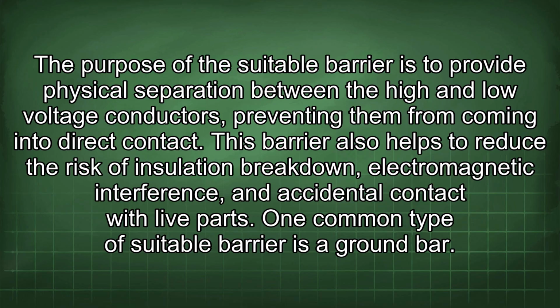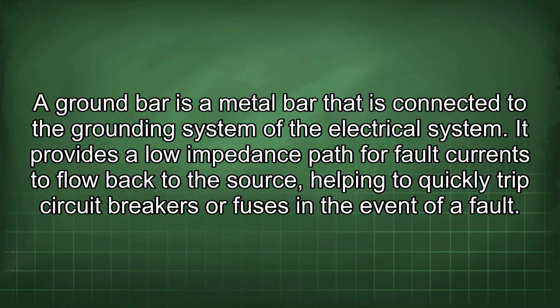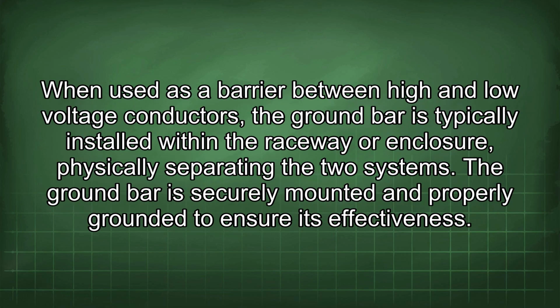One common type of suitable barrier is a ground bar. A ground bar is a metal bar that is connected to the grounding system of the electrical system. It provides a low impedance path for fault currents to flow back to the source, helping to quickly trip circuit breakers or fuses in the event of a fault. When used as a barrier between high and low voltage conductors, the ground bar is typically installed within the raceway or enclosure, physically separating the two systems. The ground bar is securely mounted and properly grounded to ensure its effectiveness.